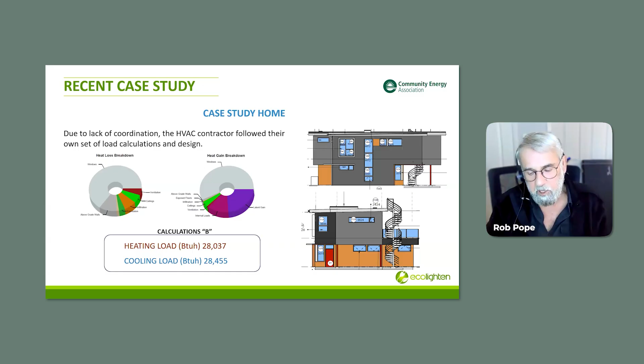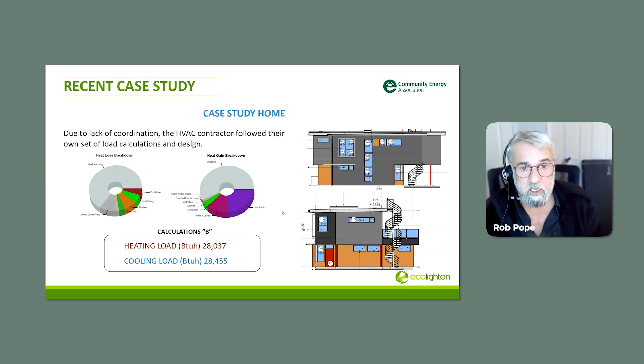We discover different equipment - first red flag. Different size ducting - second red flag. We talk to the homeowner and say, I'm not sure what went wrong here, but our design was very explicit and detailed about equipment selection, sizing, load calculations, heat pump performance curves, balance points - everything was in there, including resistance checks on the ducting. We coordinated this with you, we've got like a dozen versions to make the aesthetic work. But now we end up with this - what happened?